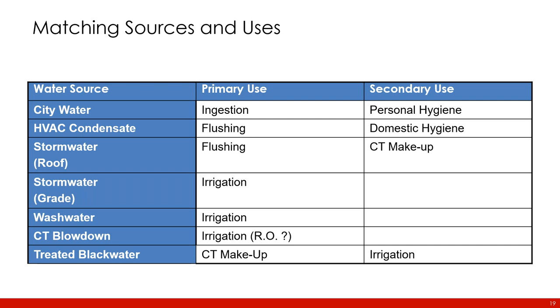irrigation. The California Department of Public Health, which has been very active in reviewing this technology, specifies that there has to be a certain distance of dirt, like 1 inch or something, between possible human contact and the delivery of this water. So you can't use wash water directly for, let's say, flushing, because it is adjacent to a human occupancy. And when you flush the toilet, it typically creates a plume of aerosols and droplets that come up into the air. And it's quite possible that your wash water might have been stored and might have grown some bacteria that might be injurious to human health.